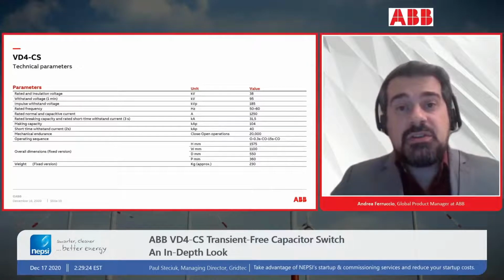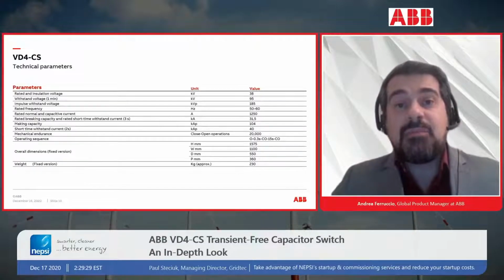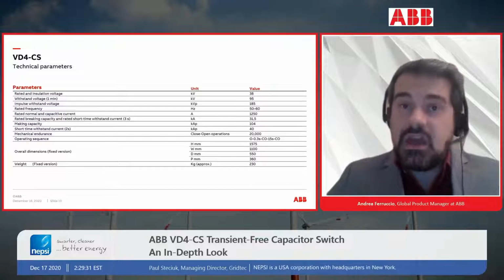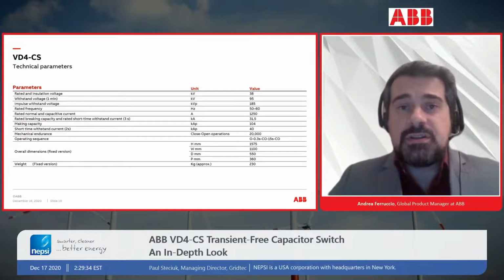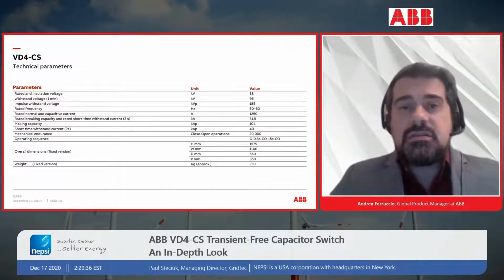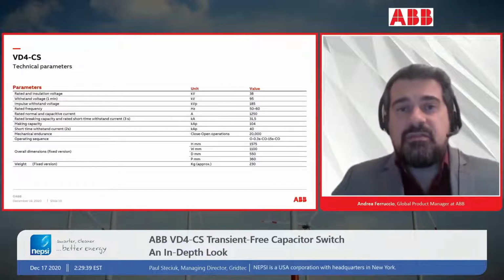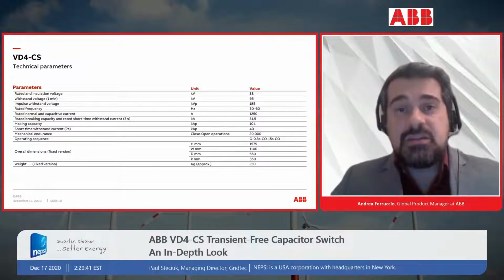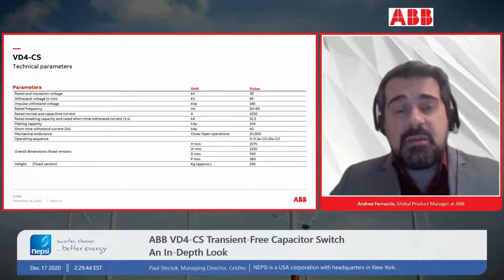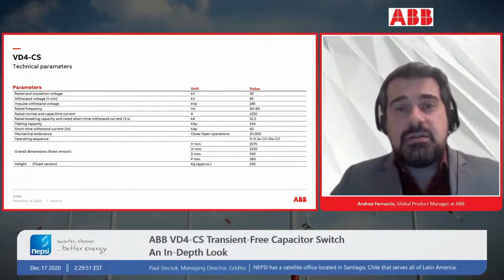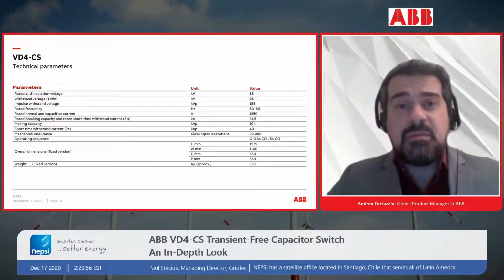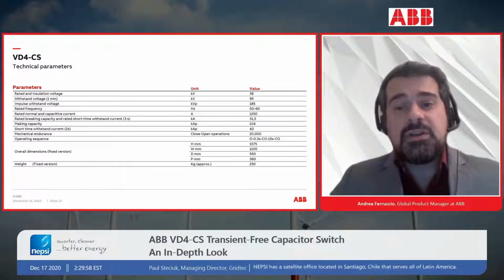thanks to the implementation of the unit synchronization, thanks to the fact that we can protect you also against short circuit up to 32 kA at 38 kV rated voltage, with a very high capacitive current, with the ability to switch a very high capacitive current up to 1250 amps. That will result, as you can imagine, in a very large amount of capacitive energy, capacitive power, that can be managed with just one unique solution.